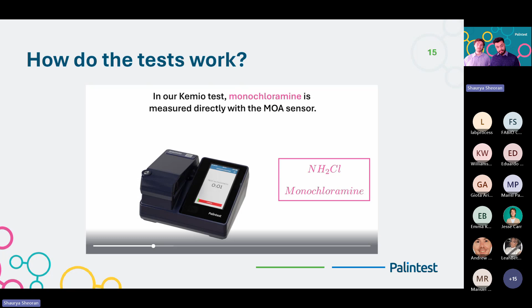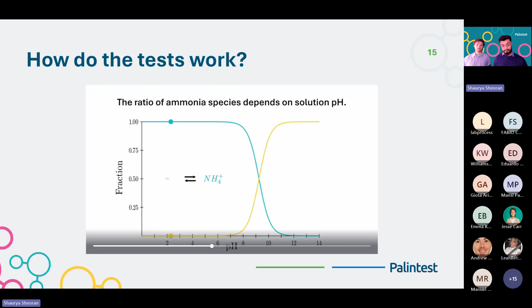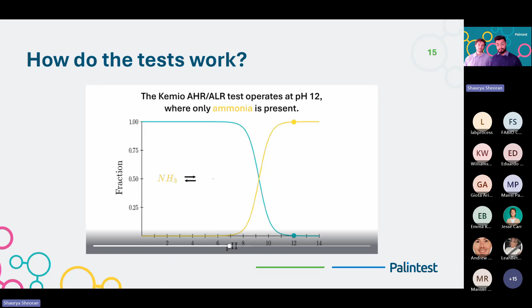So the nitrogen is in different forms. There's monochloramine, which is combined with chlorine, and then there's ammonia, which is not in monochloramine. So the sensor firstly is measuring the element that is combined with chlorine, that is the monochloramine. And this is using our monochloramine sensor, the disinfectant that you want in water. And the nitrogen which is not combined with chlorine is called the free ammonia. Now the free ammonia can exist in 2 different forms, either the ammonium ion or NH3, and it depends on the pH. They exist in equilibrium, but at very, very high pH, it's mostly present in the form of ammonia.